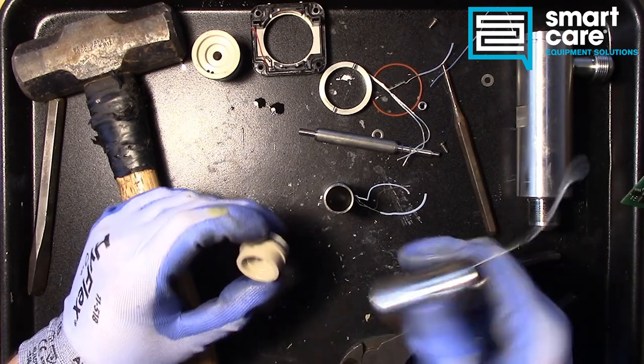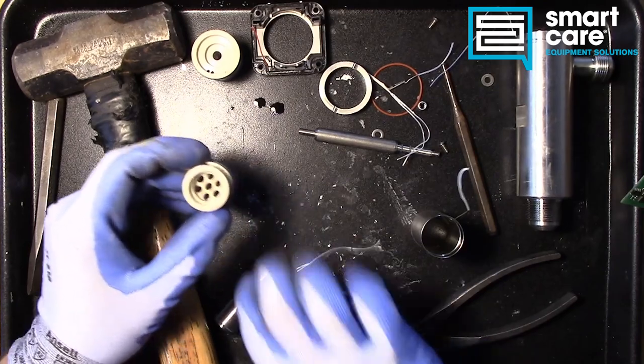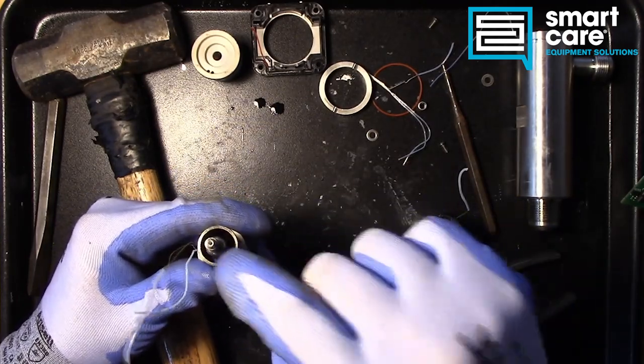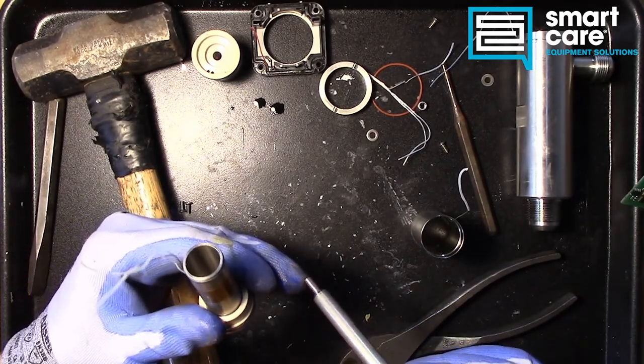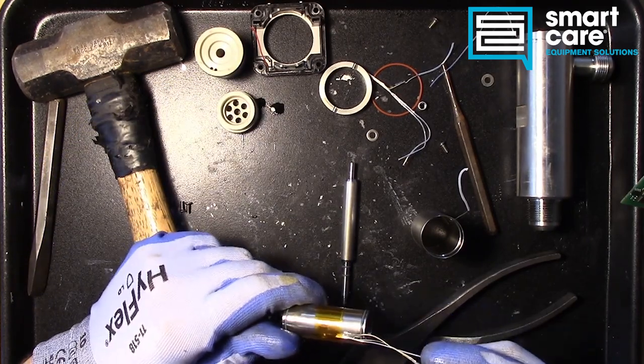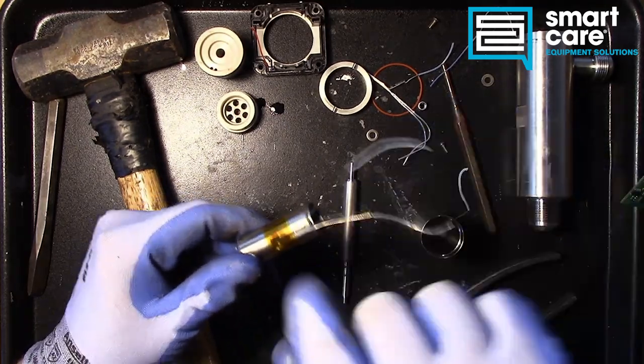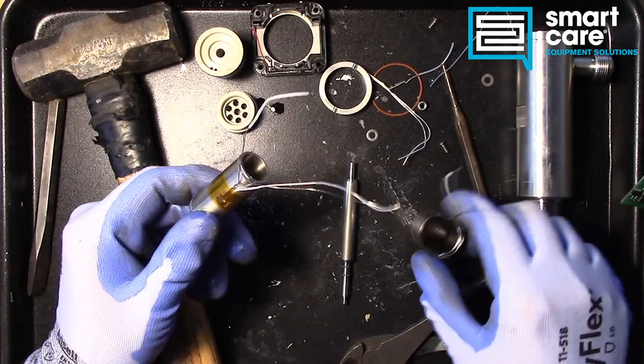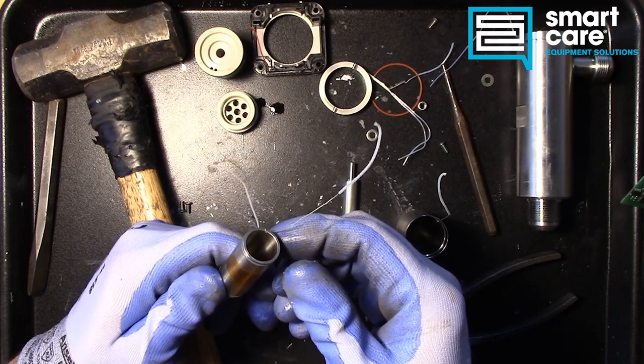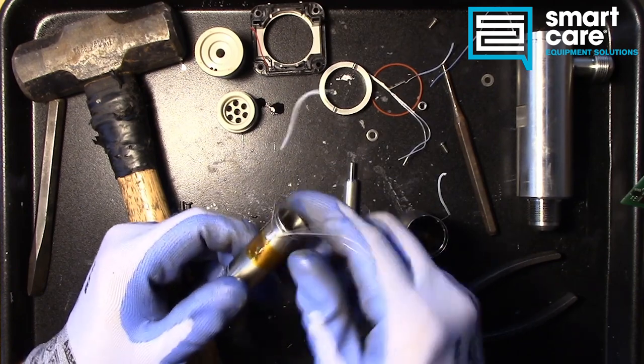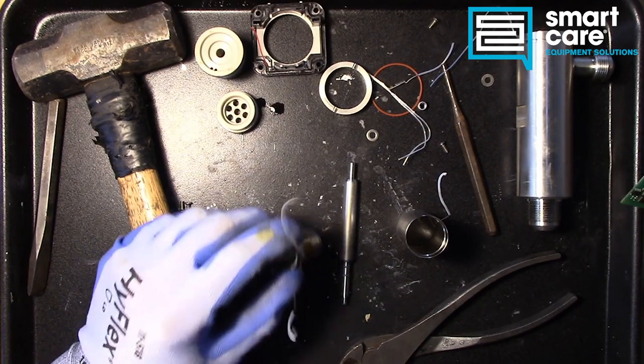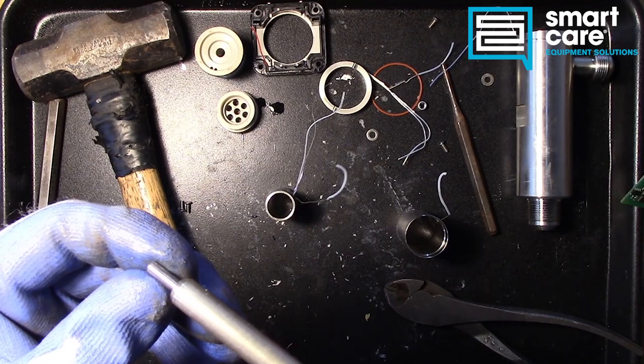So when we look at the flow path, with this being sealed down into the center like that, we just had a very precise relationship between these two metal objects, and the oil was being forced to flow in between them. The way that the surfaces are finished, I wonder if this just measured resistance of the oil, like electrical resistance of the oil. So we've got this wire soldered to the outside of that casing, we've got this wire soldered to the inside of this casing. I bet they're just measuring temperature and resistance on the oil and running it against a known table. This really looks like a thermocouple. I wonder if we hook a meter up to it if that will give us a temperature reading. Let's see if we can get this cut open though, I'm curious to see what's inside this.